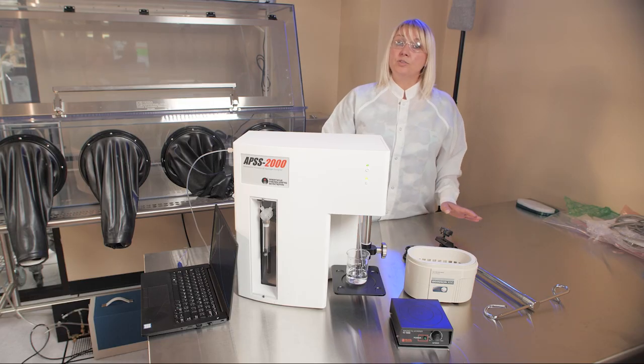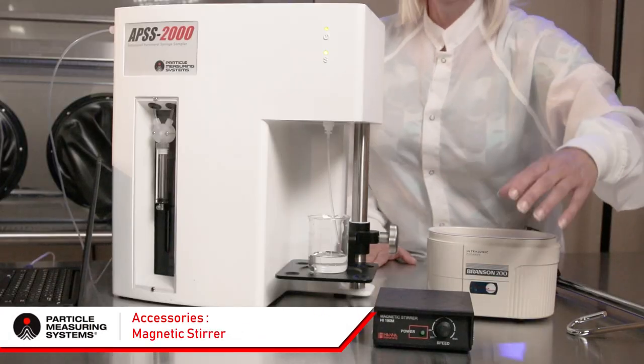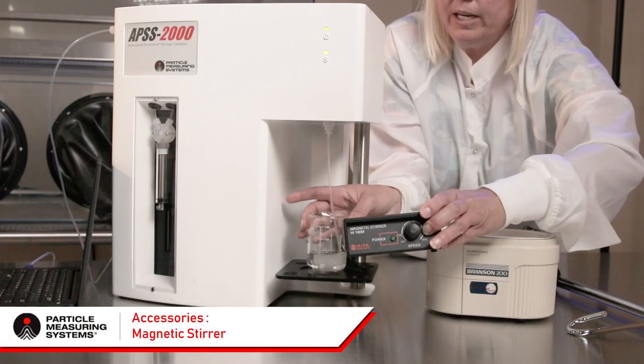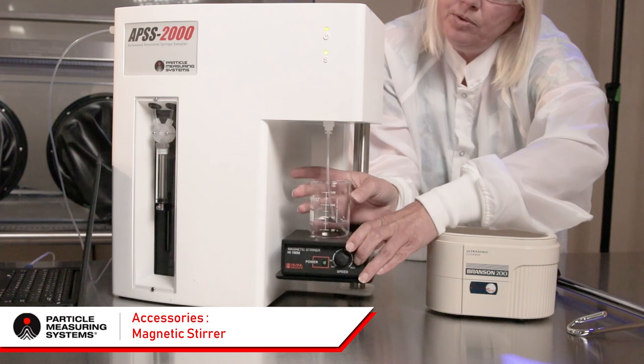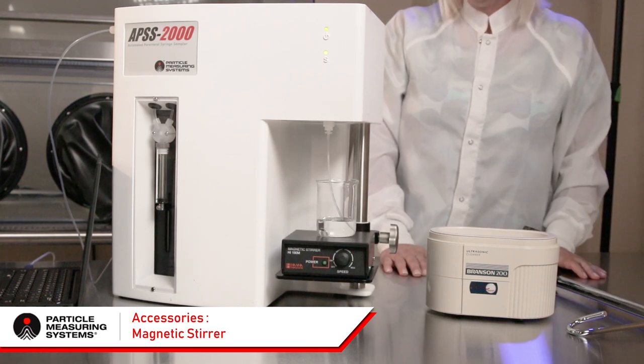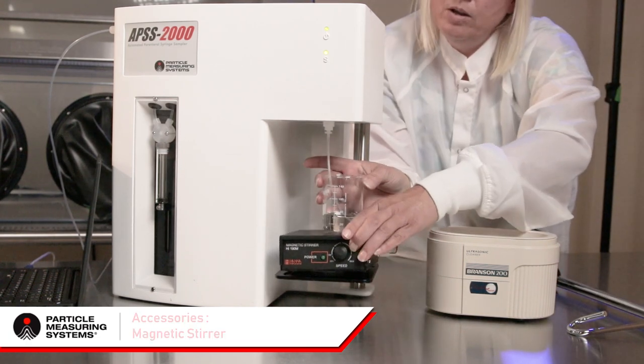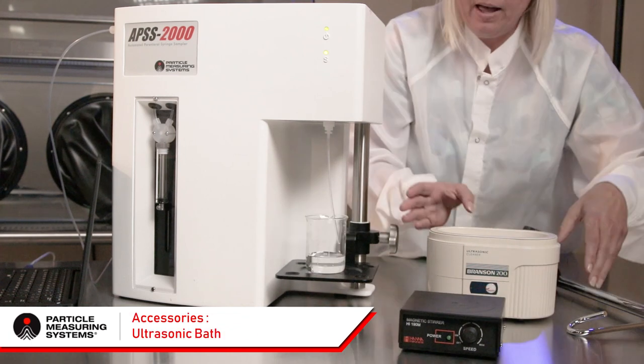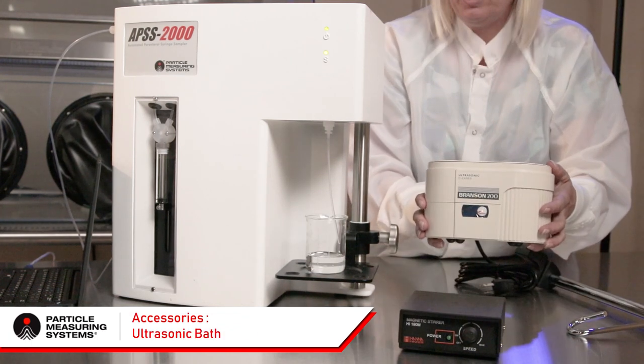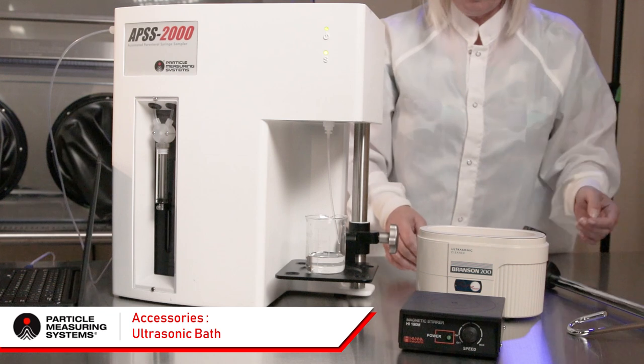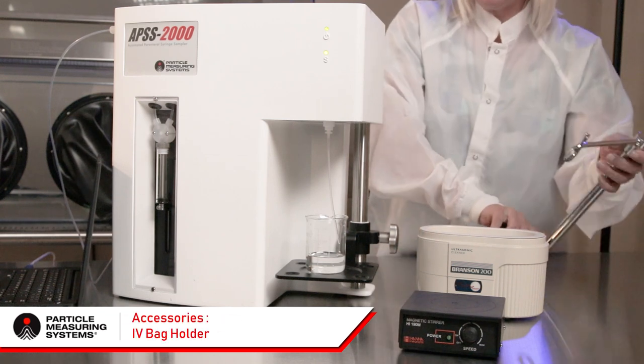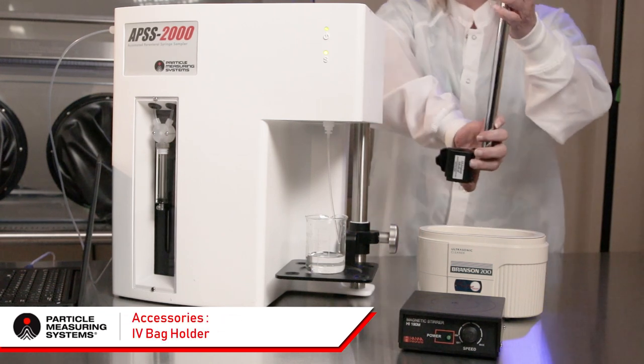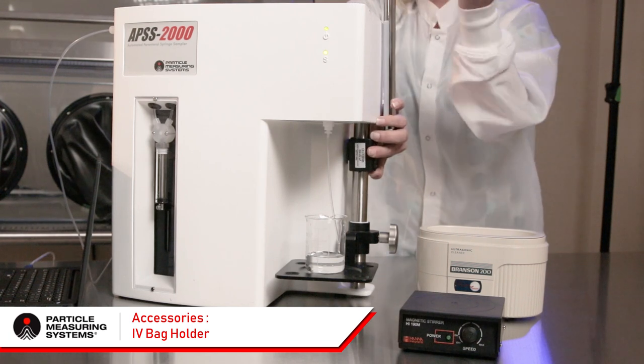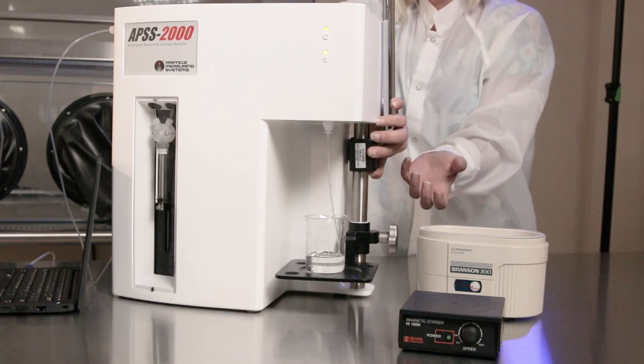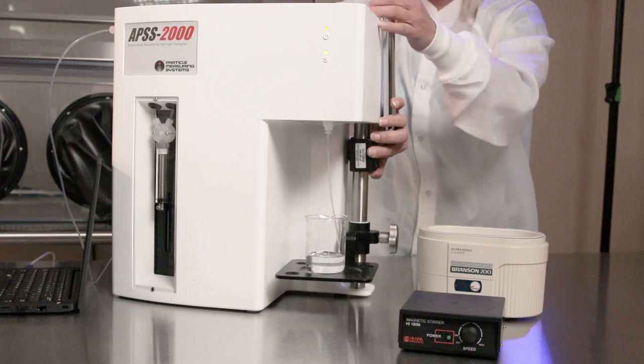The APSS-2000 has three different accessories. We have a magnetic stirrer. This is placed directly on the base, and this keeps the sample in motion for the entire process. We have an ultrasonic bath. This also keeps the sample in motion for the entire process. And then we have an IV bag holder. So if you have an IV bag, it hooks directly onto this holder and goes directly inside the instrument.